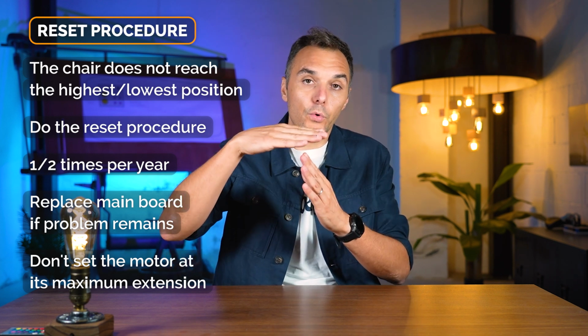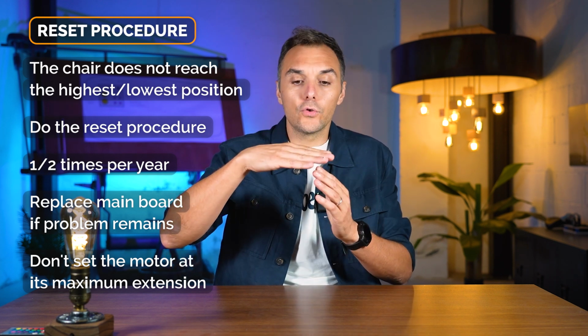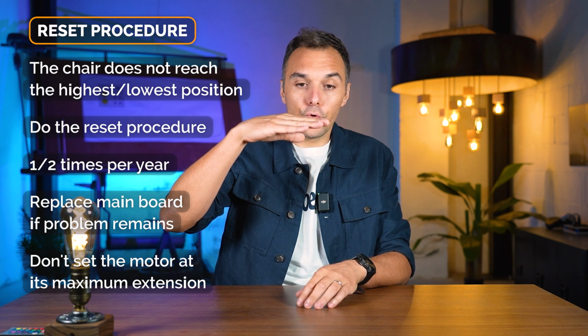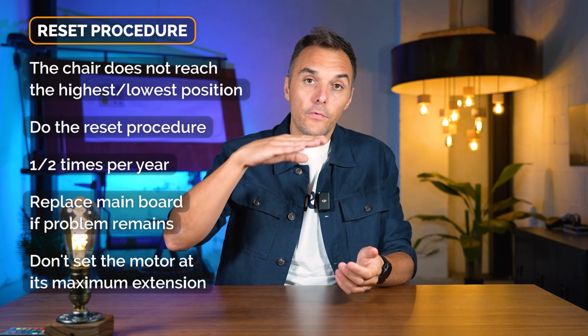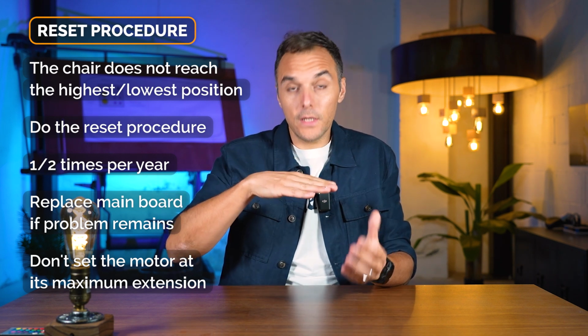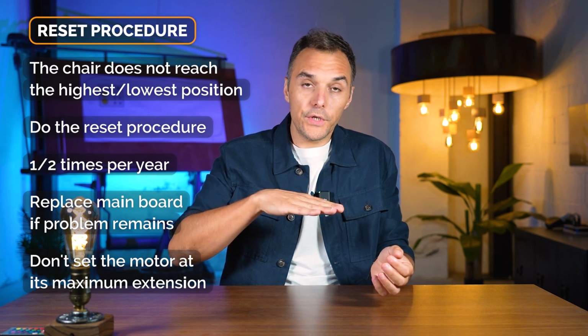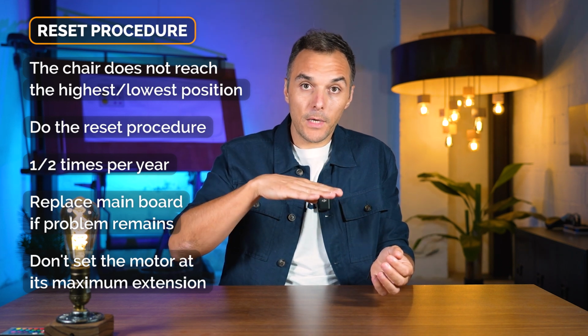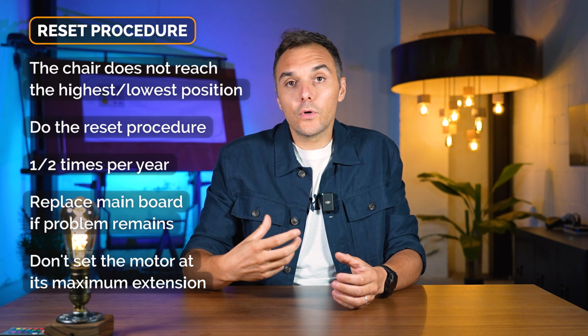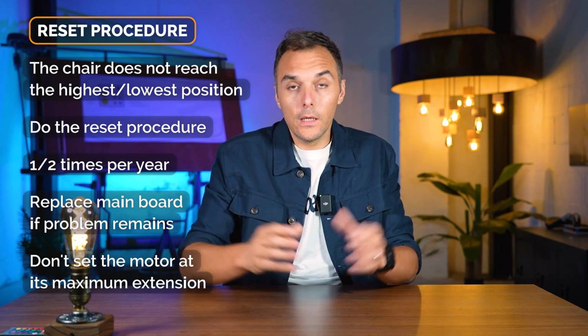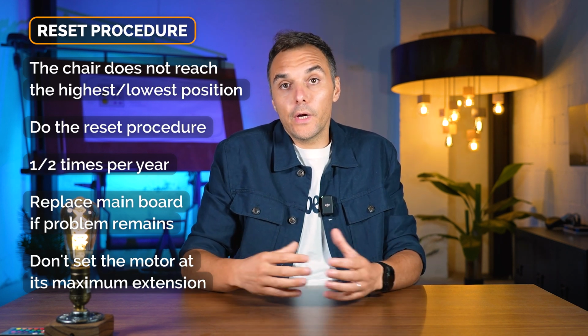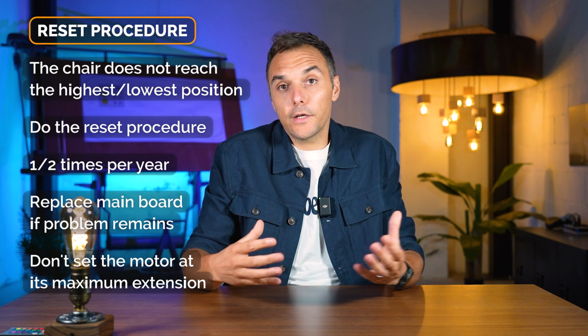So it's better if it works 1 or 2 centimeters less. You reach the upper limit and go down just a bit, and the same for the lower position of the seat and backrest - reach the lower limit, then come up a little bit. This way the motor isn't working fully, which is better because it avoids creating possible alternative problems for the dental unit.